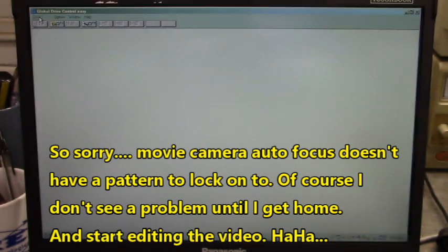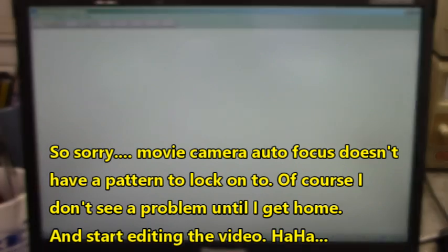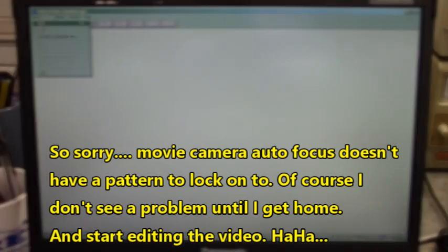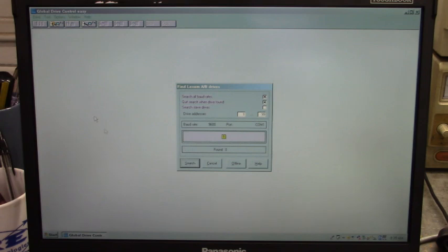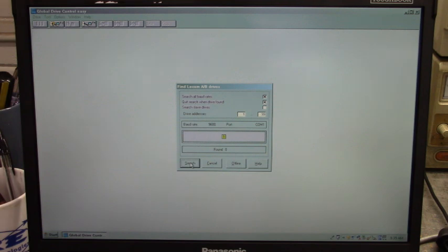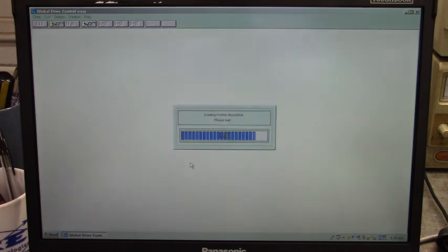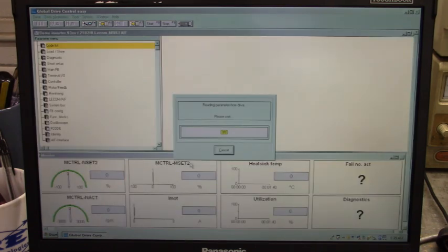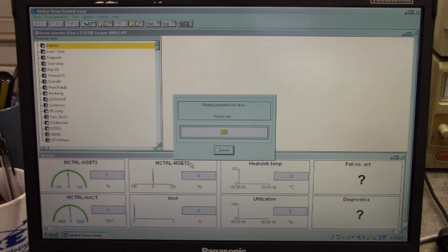Now we have to hunt for the drive. So click on the drive menu, click find, and click search. Now on this particular control board it's at address 12 at 9600 baud. There it found it. And what's happening now is it's downloading the parameters from that control board into the Global Drive Easy program.